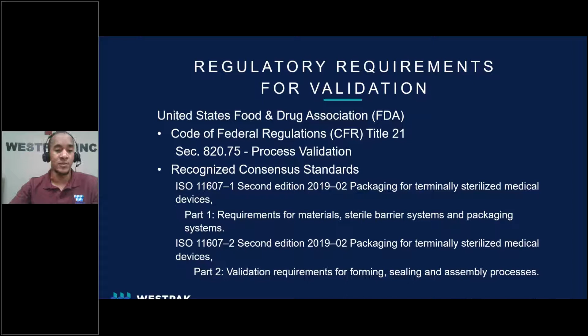The FDA also recognizes consensus standards ISO 11607, Parts 1 and 2, titled Packaging for Terminally Sterilized Medical Devices. Part 1 covers the requirements for materials, sterile barrier systems, and package systems. Part 1 of the standard is the main focus of this presentation. Part 2 addresses the validation requirements for forming, sealing, and assembly processes from a manufacturer viewpoint.